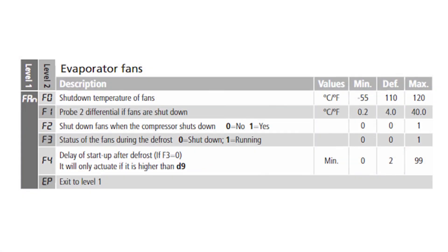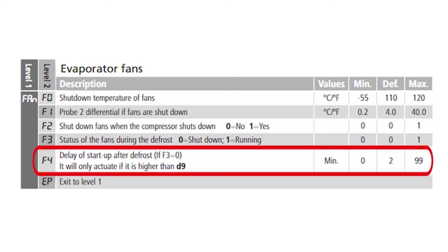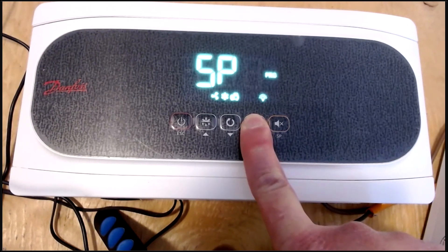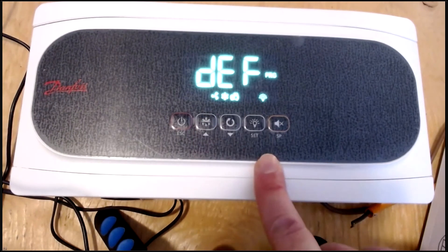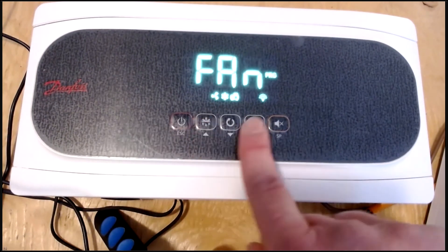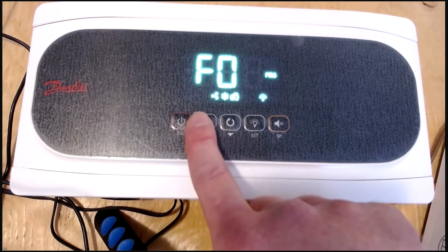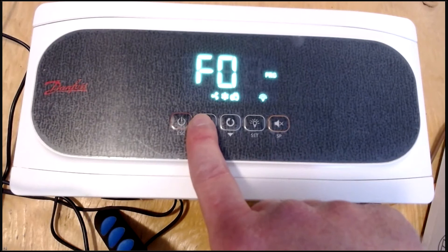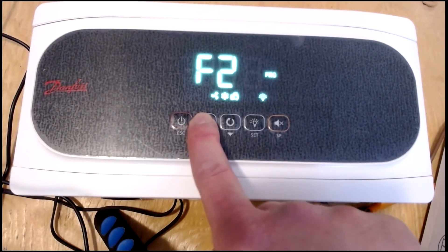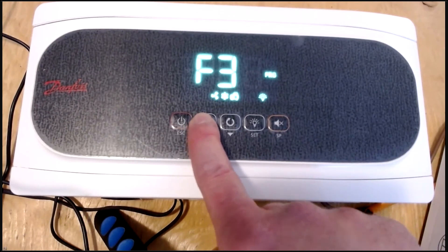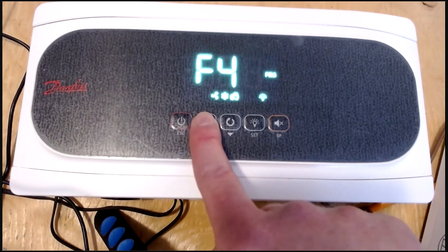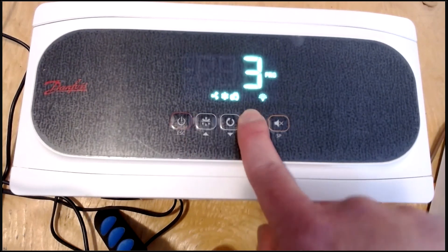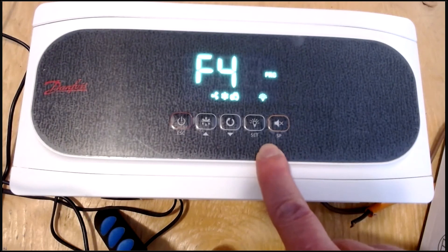Now from here, we will need to go to the level one parameter fan and select F4. So let's scroll to the level one parameter fan and hit set. From there, we will need to scroll until we see F4, which is the parameter we need to modify to change the fan delay after defrosting. There's F4 and you can see the default value is two. Let's change that to three. Hit set and we're back to the level two parameter.